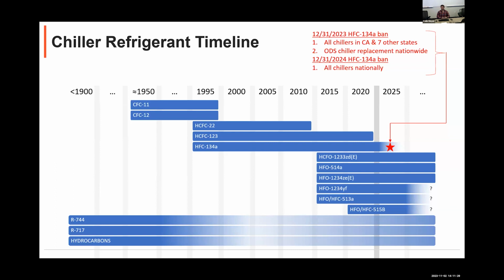And so we don't know the future of that refrigerant, but it hasn't been used in any large chillers or heat pumps yet. But the reason it's introduced is because the next one down, HFO HFC 513A, is a blend of an HFO and an HFC. It's 55% YF. It's 45% 134A. So it's actually a blend of something that is already banned and something else that might be banned. So we put a question mark on there.